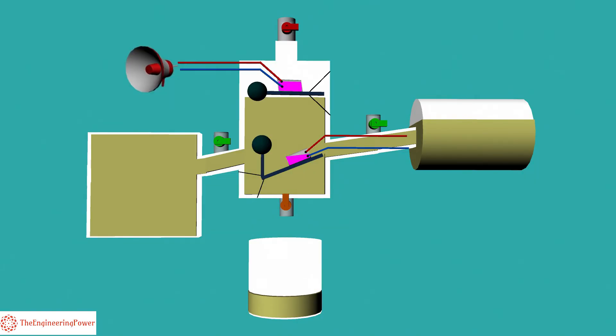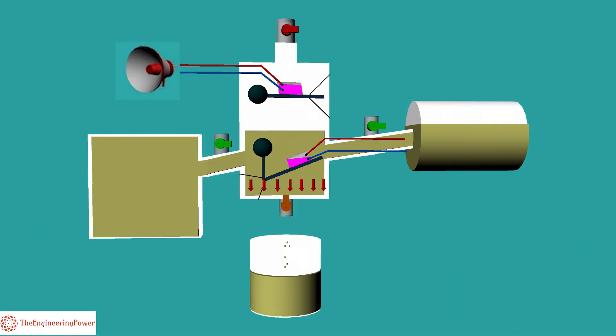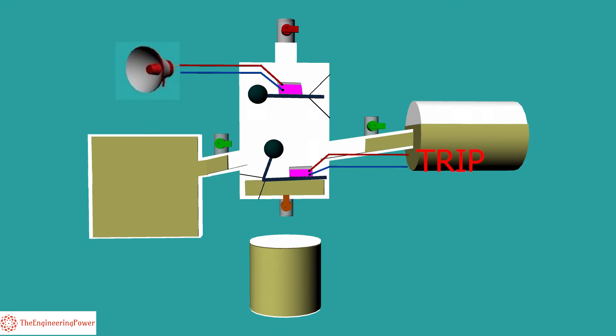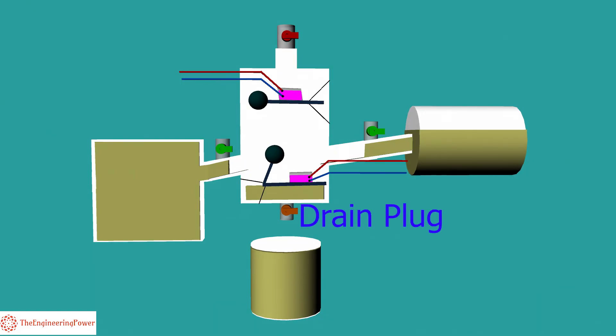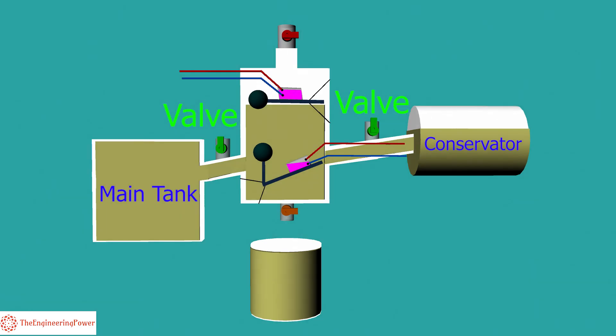First, the alarm circuit will be operated due to the oil level going down. When oil continues to be drained, the trip function will be operated. After testing, the drain plug is closed and valves from the main tank and conservator side are opened so that the relay is filled with oil again.